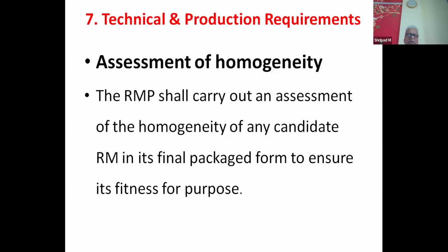In the case of liquid reference material, homogeneity is not so challenging. But in the case of solid or powder form, it is very important to maintain the homogeneity, and it is a really challenging task for everyone. So let us understand how we will go for the homogeneity. The RMP shall carry out the assessment of homogeneity of any candidate RM. It is very important at the final packaged stage to ensure fitness for purpose.